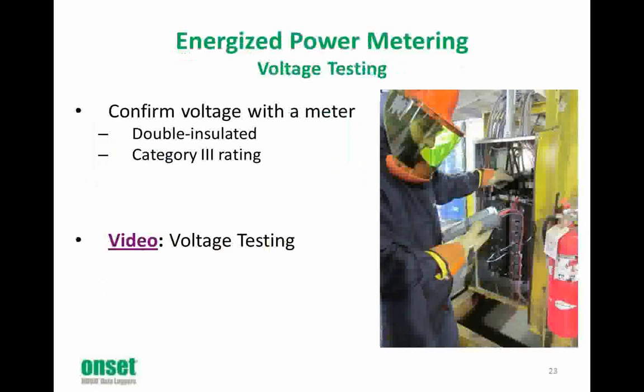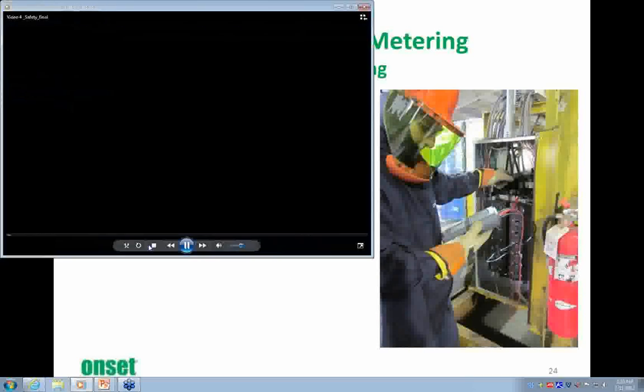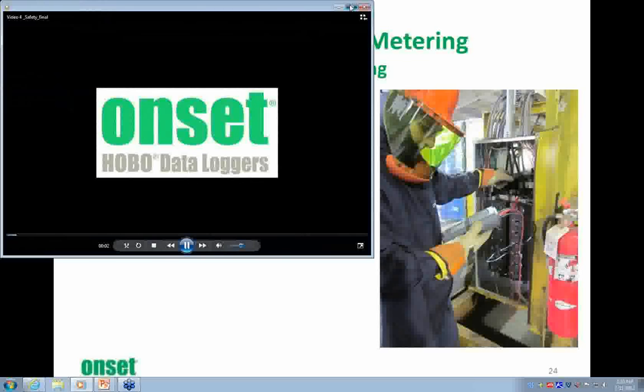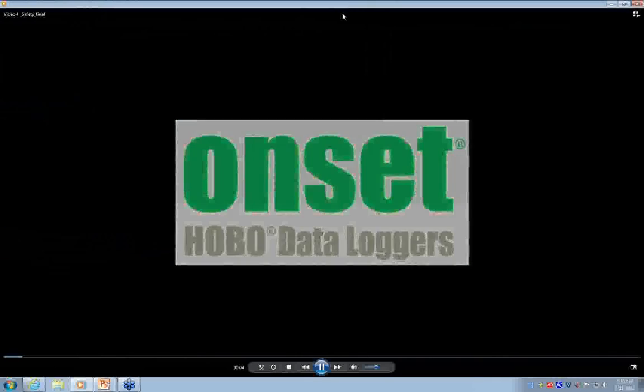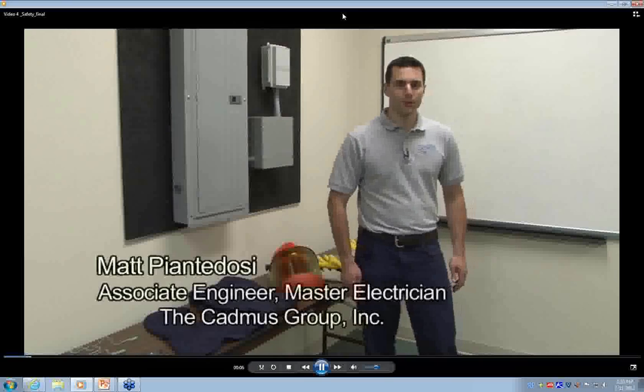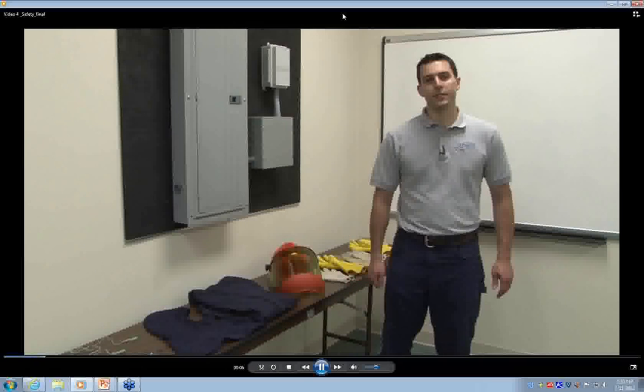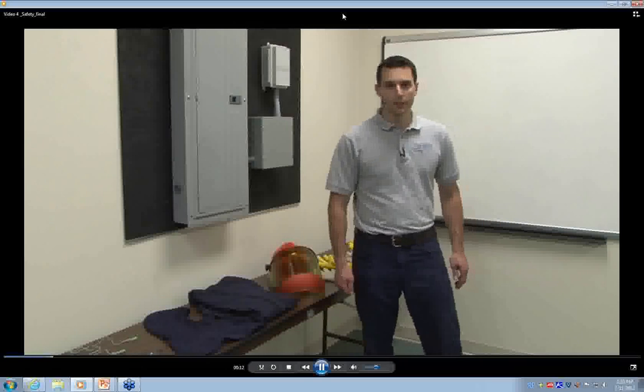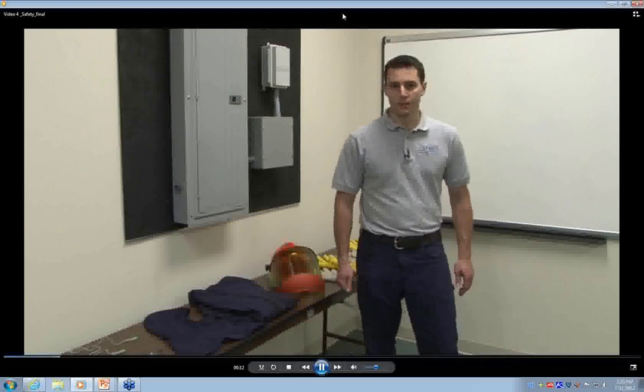Once we have a solid idea of the voltage, we should verify it with a voltage meter. It is important that the meter we use is double insulated and has at least a Category 3 rating. We will now watch a short video on how to perform a proper voltage test. We'll now perform a voltage measurement on this energized panel board. We'll do so by wearing all of the necessary safety gear that we previously described. It's important that only qualified persons enter the panel board.